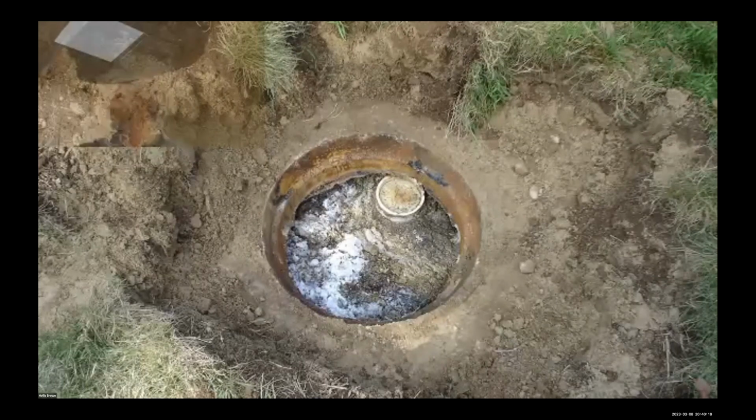That's grease. Not so easy to see, but that white stuff, if it's not toilet paper, odds are it's grease. This tank is actually backing up. The liquid level is up to the top of the tank, if that makes sense. We want to see at least 8 inches, if not 12 inches of airspace between the top of the tank and where the water goes out.